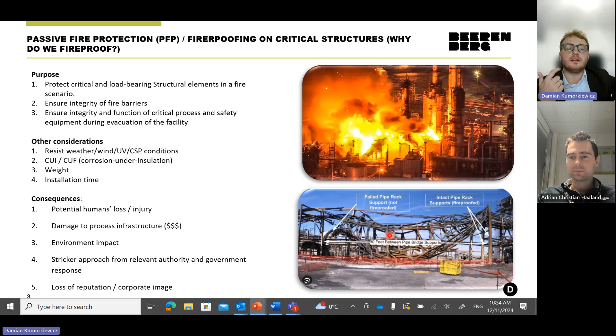We would like to briefly mention how relevant structures are defined for PFP. During the fire risk assessment, normally performed by technical safety, process safety, or HSE engineering departments, representative scenarios are selected through initial fire risk analysis. This process evaluates leak frequencies, ignition probabilities, and inventories to identify the cases with the highest risk areas. The goal is to determine the fire loads and design accidental loads, which guide fire protection measures.